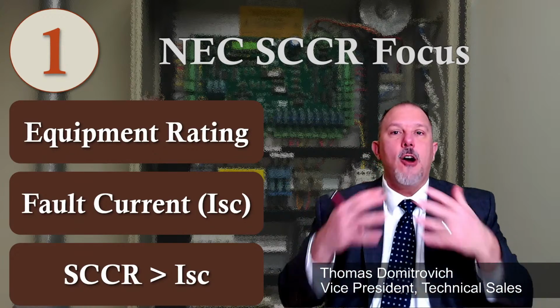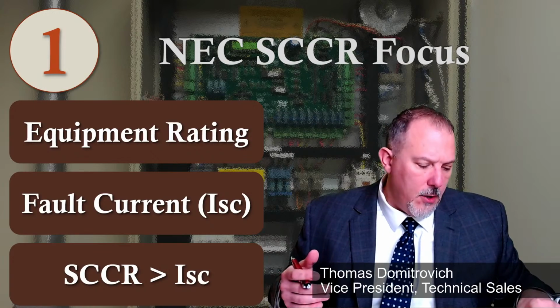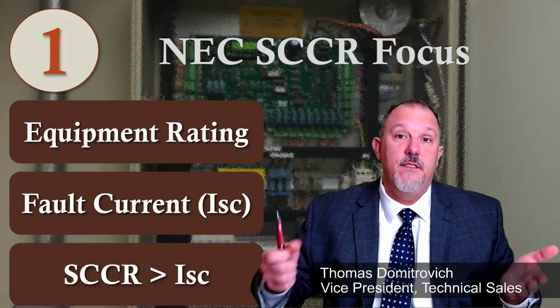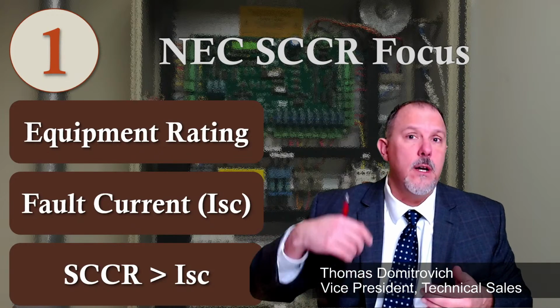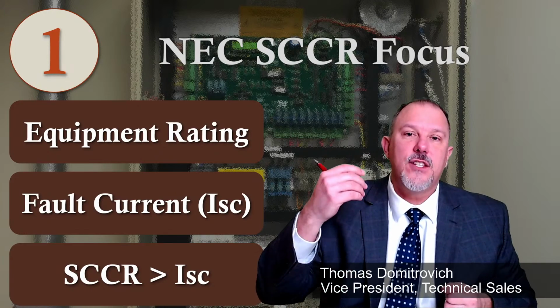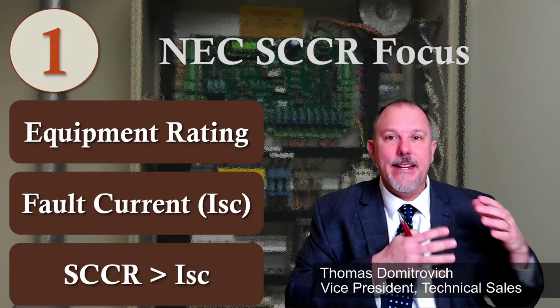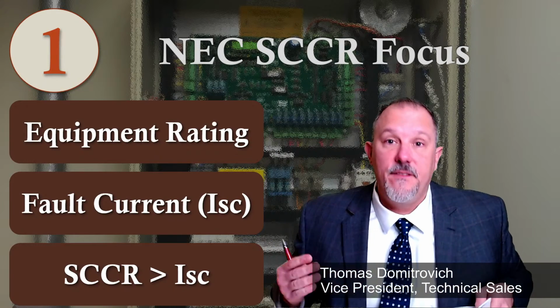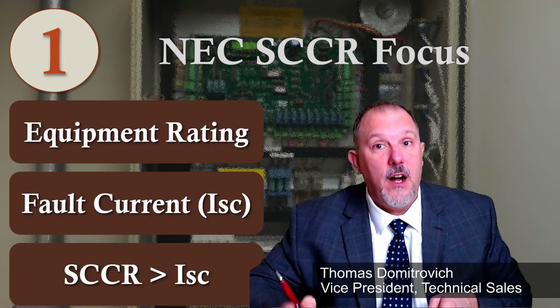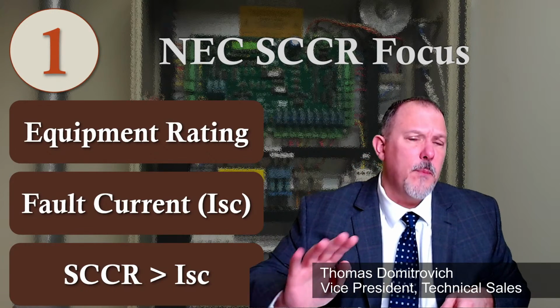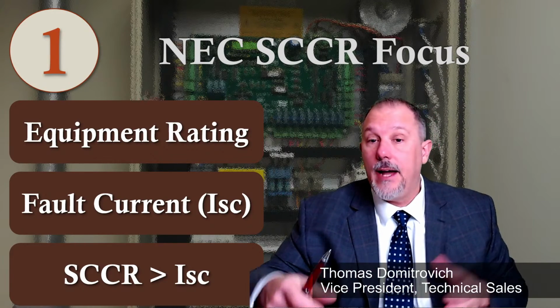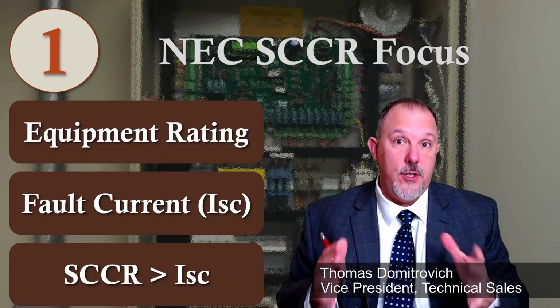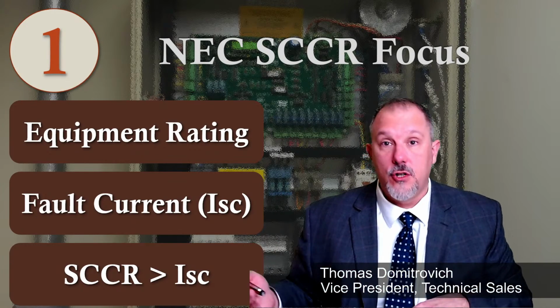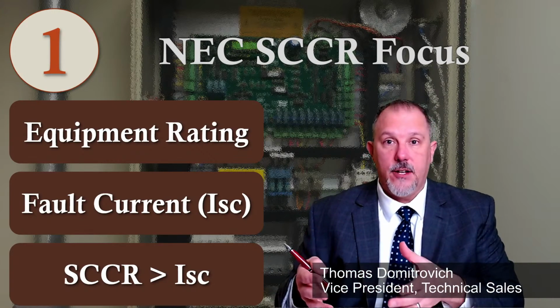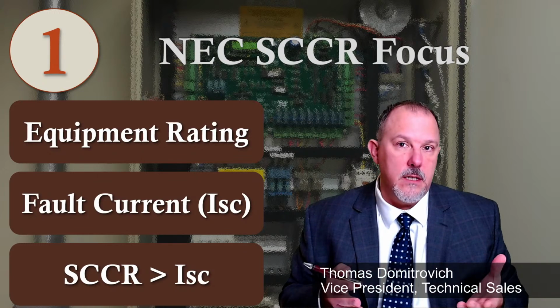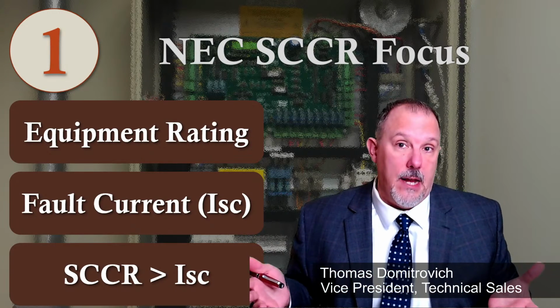So we're providing options. In the circuit breaker world, and you look at our panelboards and switchboards, you'll see various options available for electricians, electrical contractors, and design engineers. It's very important to provide options. That industry, from breakers to panelboards and switchboards, has been doing that for years. Here's where things become a little bit newer for other equipment manufacturers. HVAC is doing a pretty good job of providing options for higher than 10K. I would say the low-hanging fruit for opportunity to provide options is, in my opinion, in the elevator control panel world. Your elevator manufacturers have control panels. Unfortunately, many of those are only listed and rated for 10,000 amps. I don't know of any that are rated for greater than 10,000 amp short circuit current rating.